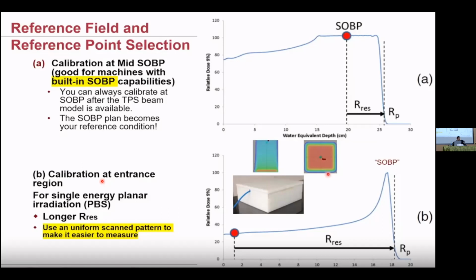And there's different ways to do it. You could do an SOBP or you could do it by a single point here. On the physics here, there's a reciprocity theorem that if you do a small beam with a big detector, the inverse of that is going to be a small detector, like a Farmer chamber or something small, and a big beam, right? So you could get the same type of answer. The whole point is you want to make sure you're collecting everything of importance.